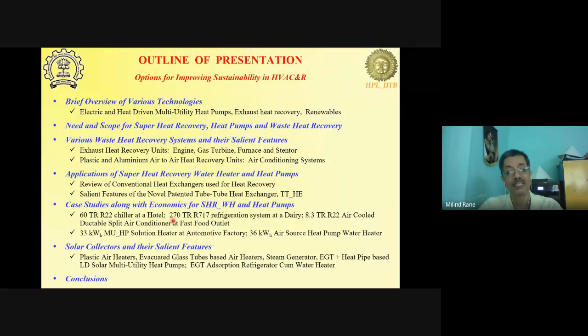We'll then look at the 270-ton ammonia refrigeration system based superheat recovery water heater, heating water from 25 to 75, 80, 84 degrees centigrade. Then we'll look at a hot water heating system for a fast food outlet. And these were deployed in McDonald's, and more than 340 of them are deployed in various McDonald's at one point. And then we'll look at multi-utility heat pumps.